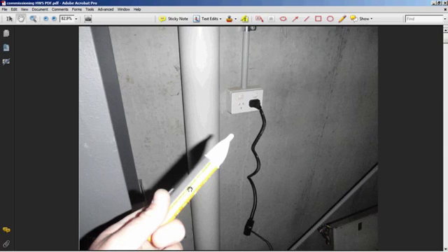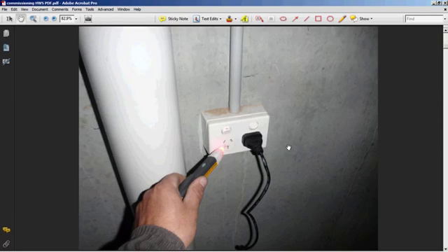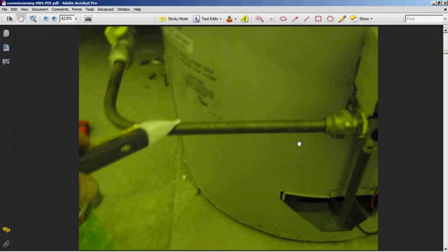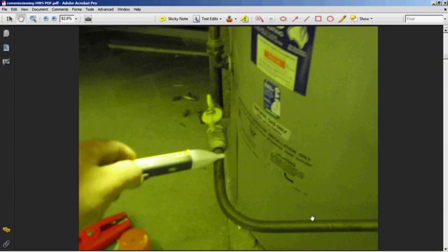First, you need to test your neon tester to ensure that it is working as it should. It's no good using a neon tester that is not working or the batteries are flat, so even if there is stray current there, it's not going to pick it up. You test your neon tester as shown here on a known power source. Then you go about testing the copper pipework with the neon tester, make sure it doesn't liven up in several places. And then you also must make sure you test the casing of the appliance to make sure that isn't become live somehow.